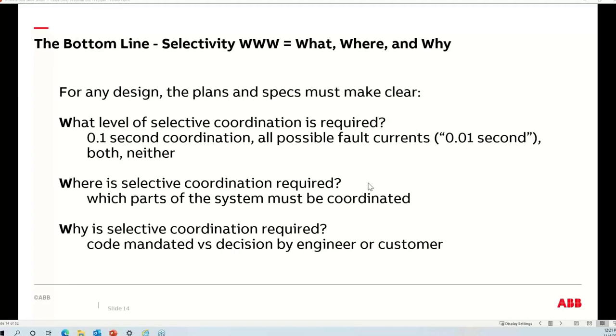From the perspective of the specifier, I'd sum it up with the three W's: what, where, and why. Before you send your project out, see if you can quickly answer these three questions without relying on your in-depth knowledge — or give it to a peer in the office who hasn't worked on the project. The 'what': what level of coordination is required? What definition are we using — is it 0.1 second, or the formal Article 100 definition we informally call 0.01 second coordination? That should be very clear and quickly discernible.